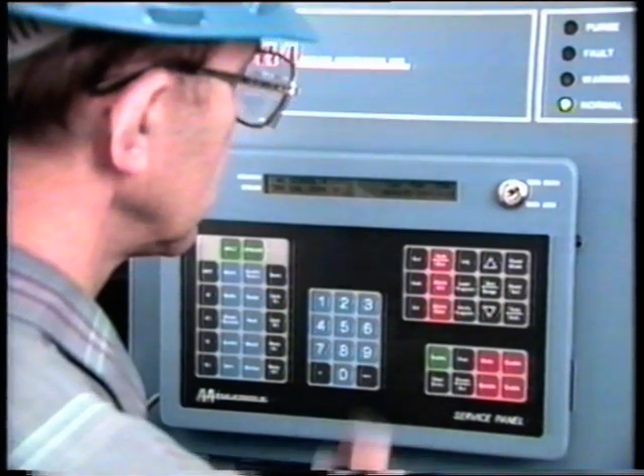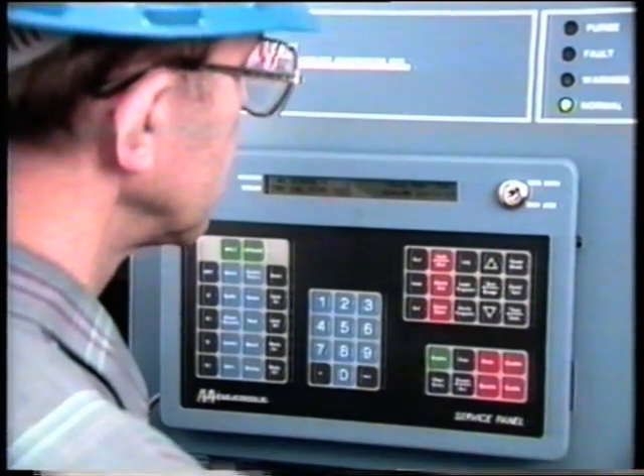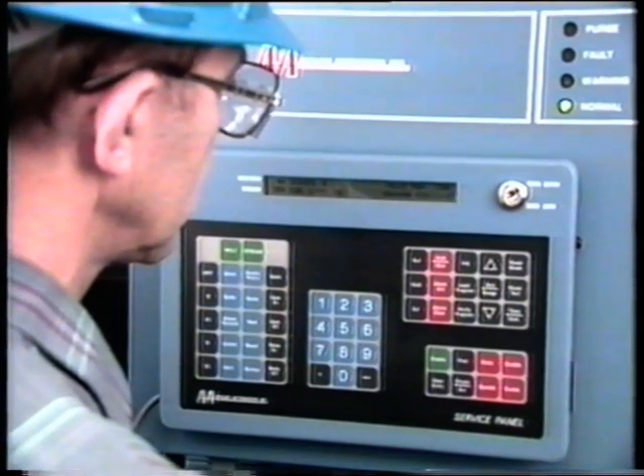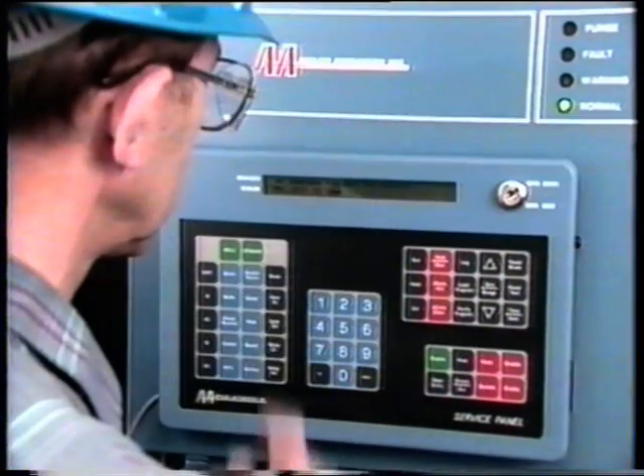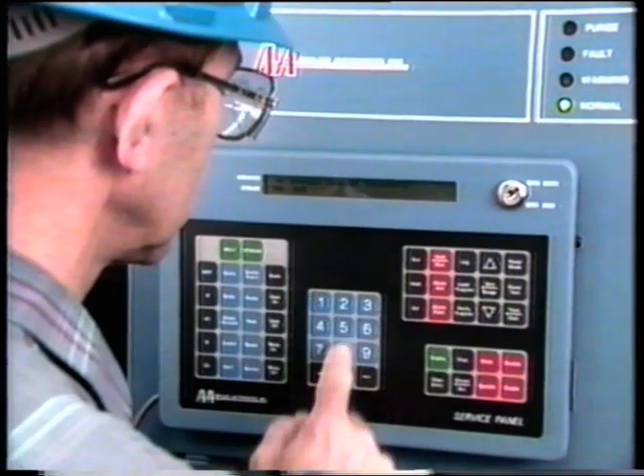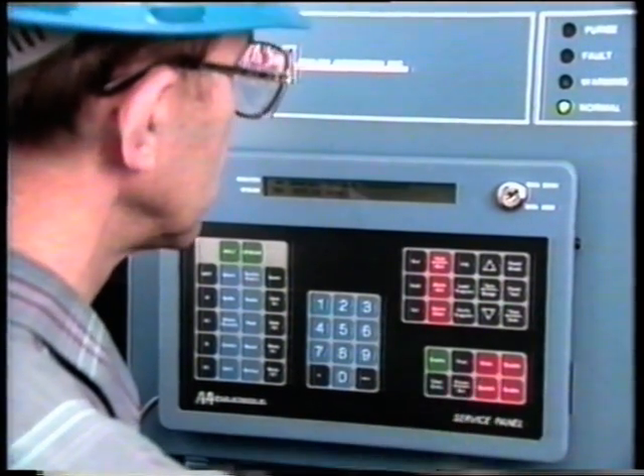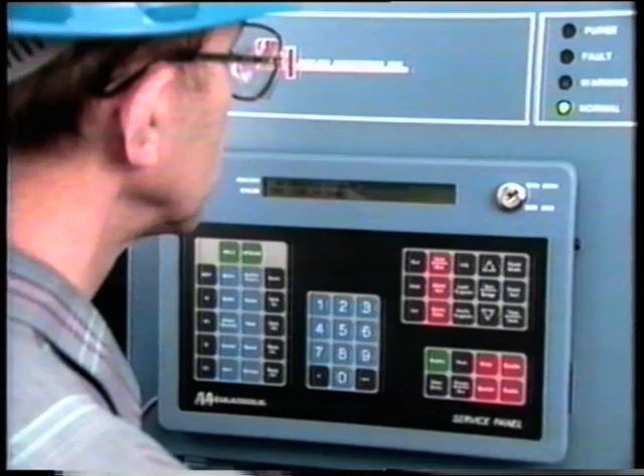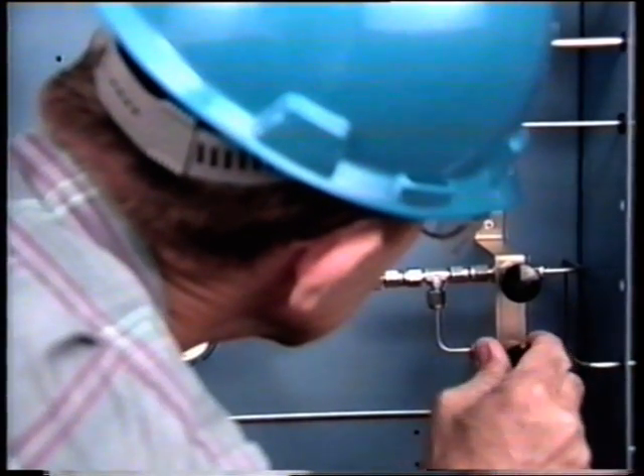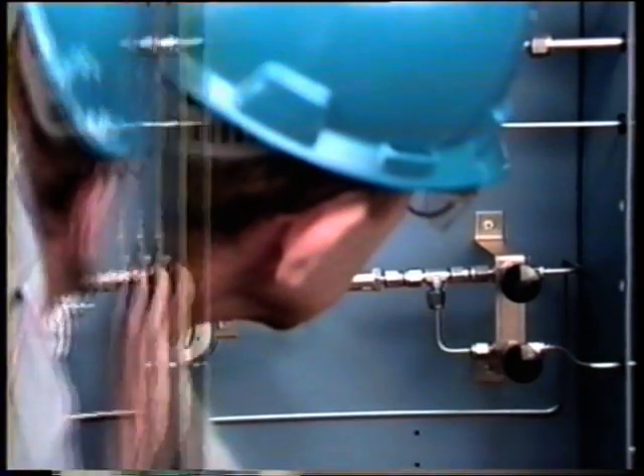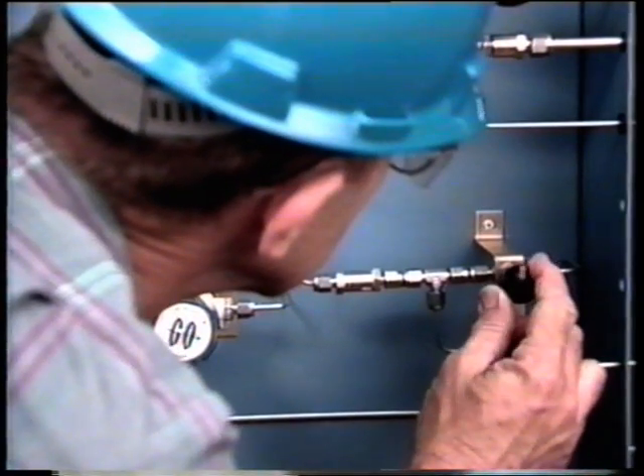When you're satisfied with the chromatogram, press Hold and wait until the current calibrate cycle is complete. Press Event 10, Operate. This updates the new calibration factors. Turn off the Calibrate flow valve. Now, you can restart the sample stream.